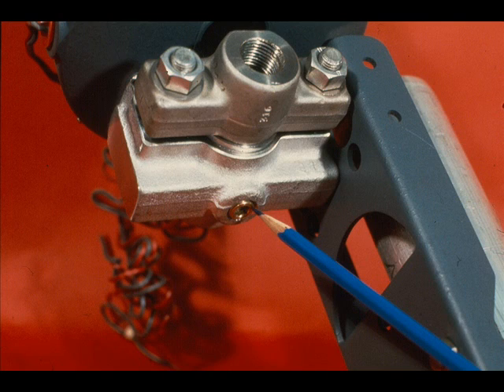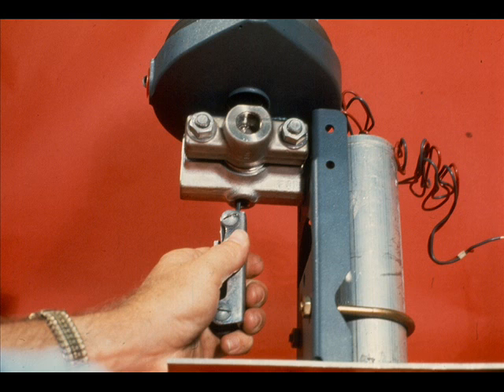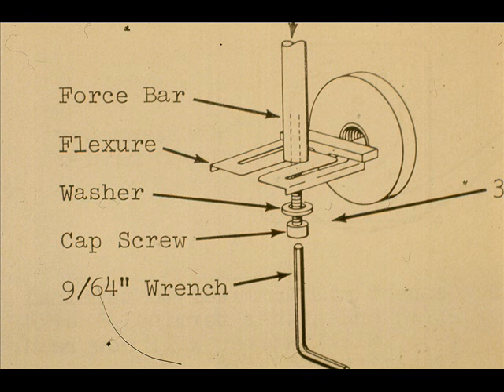We are fortunate — we already have the link arrangement in place. We will proceed to install the C capsule in the transmitter. The capsule has the letter C stamped into it. First, remove the strainer vent plug located at the bottom of the transmitter.